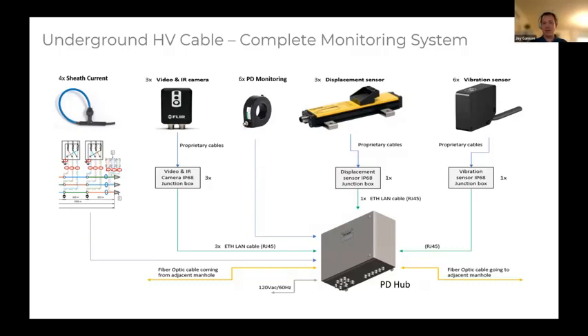PD monitoring is the best input that we can have into the insulation of the cable system, and so that's really going to give you the information and the warning about potential problems. And we use displacement and vibration sensors to make sure that the cable, when it's installed, is staying on top of the cross arms, and also that there's no external interference with that cable, whether it be construction, street work, road repair, anything that might impact that critical infrastructure. So we've taken all of these different elements and tied them into our PD hub and bring all of this data back.